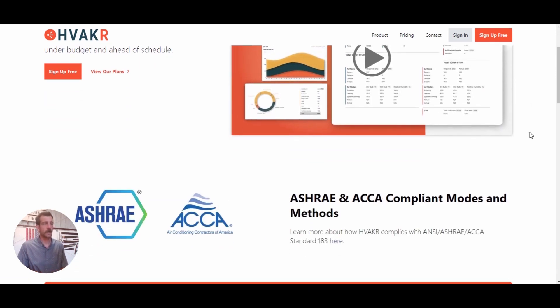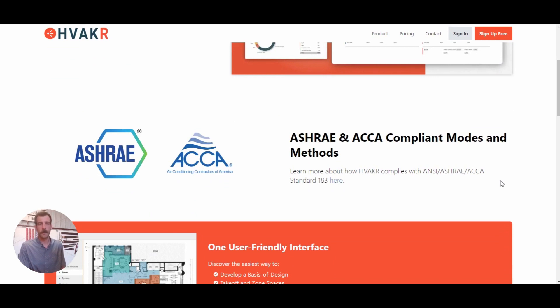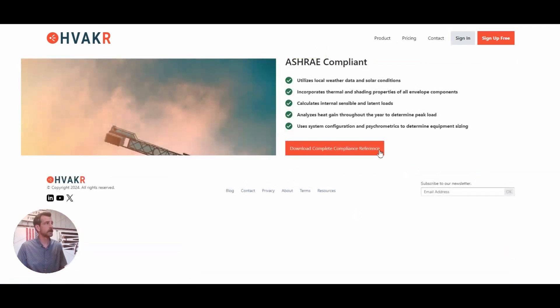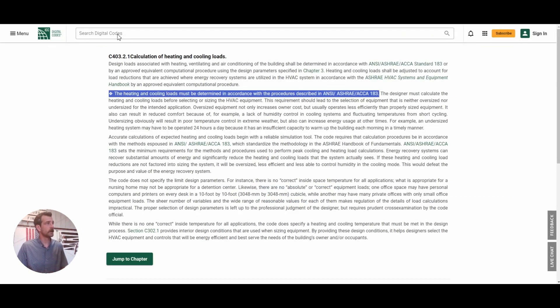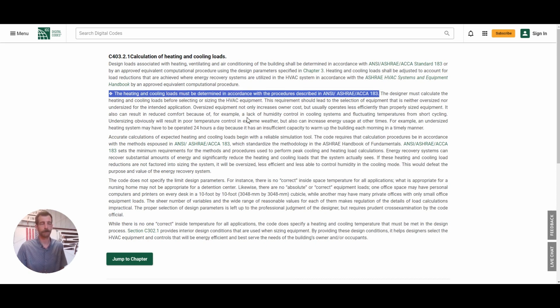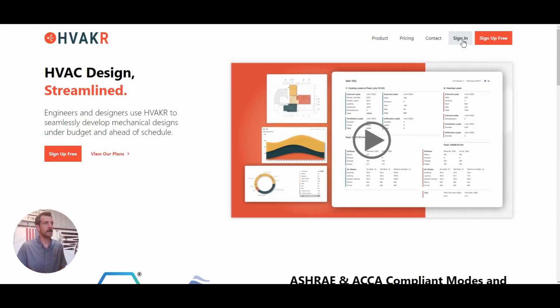A quick note about codes and standards. HVAKR is a professional load calculation program that can be used for both residential and commercial. In residential, we're talking about houses. Manual J is one of the most common methods for load calcs — that's the one you're probably going to hear — but there are other methods. ACCA, who put out Manual J, also got together with ASHRAE and developed Standard 183. So you can use HVAKR for your own personal benefit, or if you need to print a report and go through plan check. If you dig into the ICC codes, you'll see that ANSI ASHRAE ACCA Standard 183 is the requirement for heating and cooling loads — basically, Manual J is not the only option.